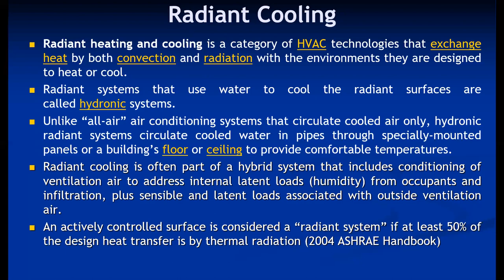An actively controlled surface is considered a radiant system if at least 50 percent of the design heat transfer is by thermal radiation. This is as per ASHRAE standards, 2004. If the building walls or control surfaces absorb heat due to radiation for at least 50 percent, then and only then the system is regarded as a radiant system.